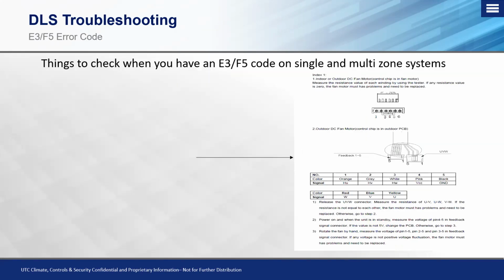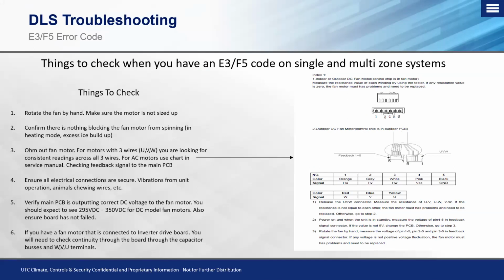So things we want to keep an eye out for when we're looking at an E3 or an F5 code on a single and multi-zone system. Some things that we want to check first and foremost are going to be basic stuff. We're going to want to rotate that fan motor by hand. Of course, you're going to want to power the unit off. You're not going to want to do this while the unit is trying to run. Of course, if you're getting this code, the outdoor fan motor is not going to run anyway, but as a good safety measure, we always want to make sure that we power that disconnect off. So once we have the power off, we want to go ahead and rotate that fan by hand and make sure nothing's seized up with the motor. And of course, if that fan motor is not spinning freely, then you may have found your issue.